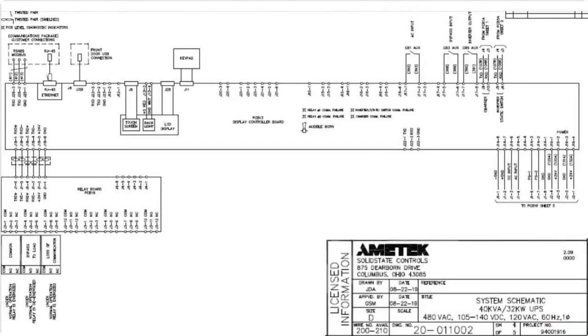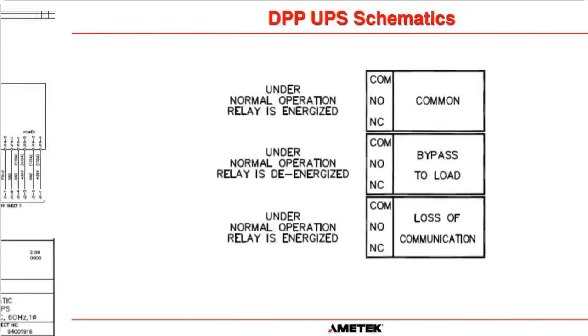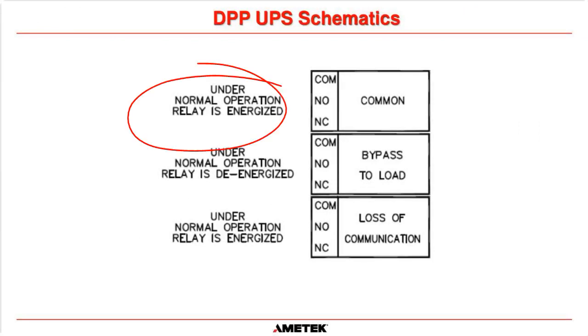And what I wanted to do with that, this is the relay board here. I've turned it 90 degrees so you can see it better on this next page here. We try and make it as easy as possible for you, okay? So we're saying for the common alarm, under normal operation, the relay is energized, okay? So we're saying if there is no alarm, the common alarm is energized. So unfortunately, relays and alarm contacts get so many people confused. And I understand why. I sometimes get confused myself, but we're trying to make it easy here. So what we're saying is, if everything is healthy, this common alarm will be energized.